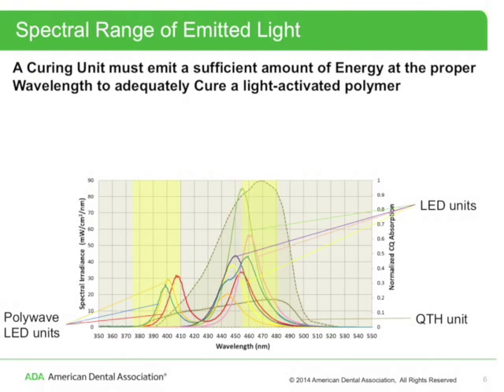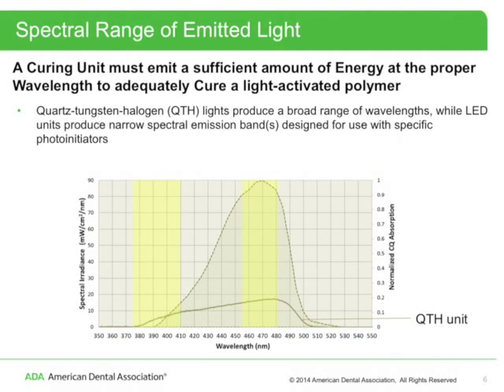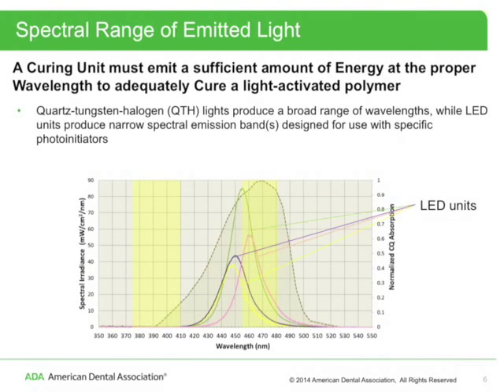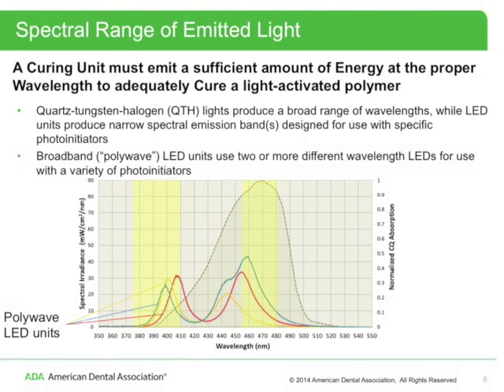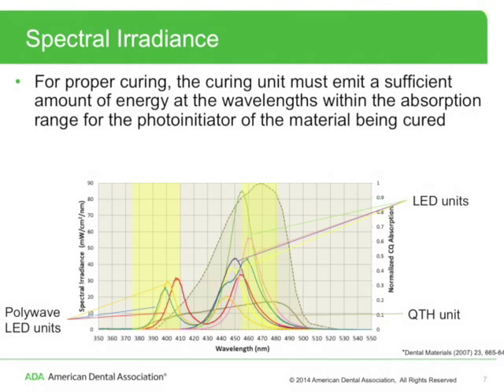A curing unit must emit a sufficient amount of energy at the proper wavelength to adequately cure a light-activated polymer. This figure displays representative spectral emission curves for several single-peak LED curing units, along with a few poly-wave LED curing units and a quartz tungsten halogen unit. Quartz tungsten halogen lights produce a broad range of wavelengths, while LED units produce narrow spectral emission bands designed for use with specific photo initiators. Broadband or poly-wave LED units use two or more different wavelength LEDs for use with a variety of photo initiators. For proper curing, the curing unit must emit sufficient energy at wavelengths within the absorption range for the photo initiator of the material being cured.